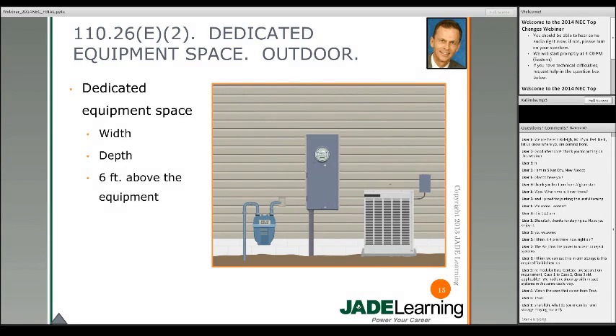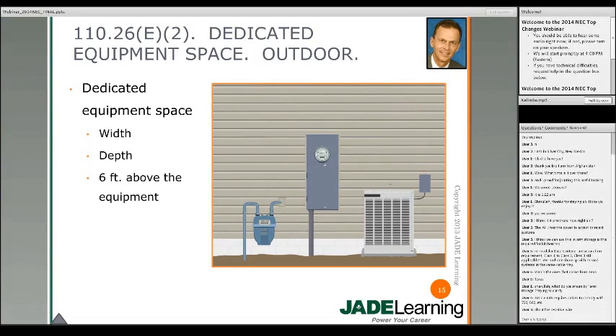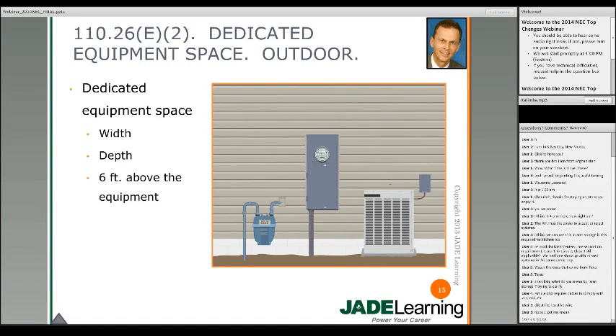No piping or other equipment foreign to the electrical installation shall be installed in that zone. Once we get above that six-foot zone, foreign systems are permitted, but protection is required. This section pertains strictly to dedicated equipment space — it's dedicated for the electrician to install wiring methods getting to the switchboard, panel board, switchgear, or motor control center. That's why it's just these four particular pieces of equipment. For something like an automatic transfer switch, once those wiring methods are in place you wouldn't be going back later to install additional wiring methods.